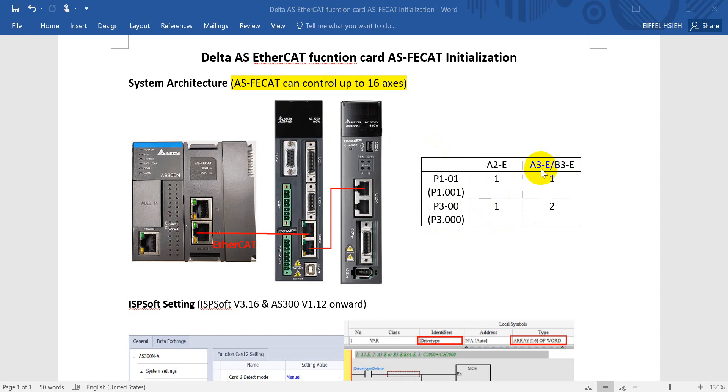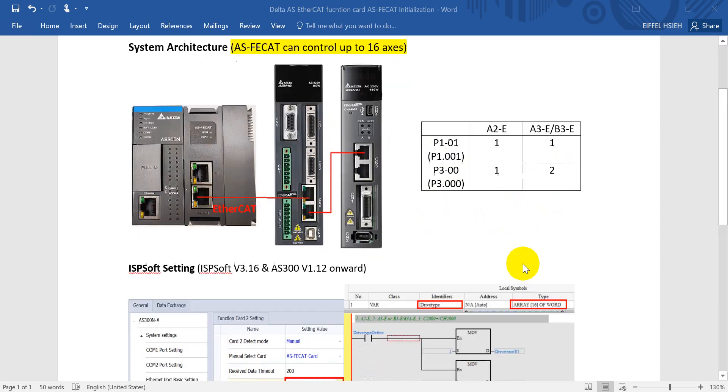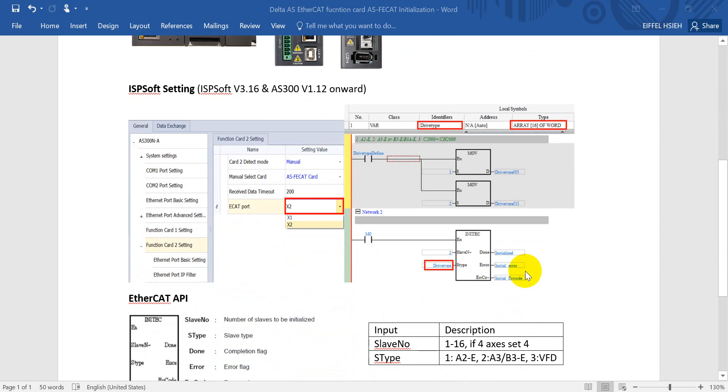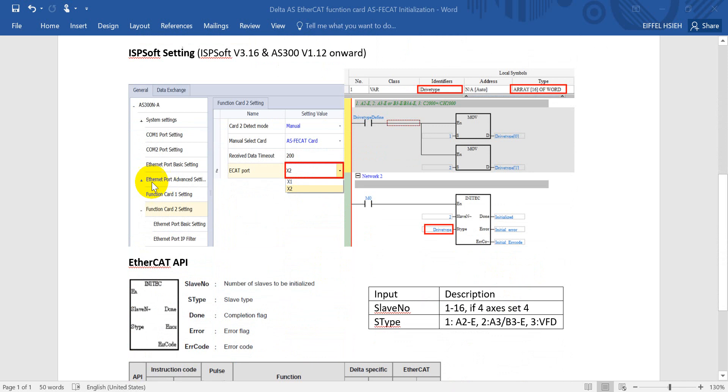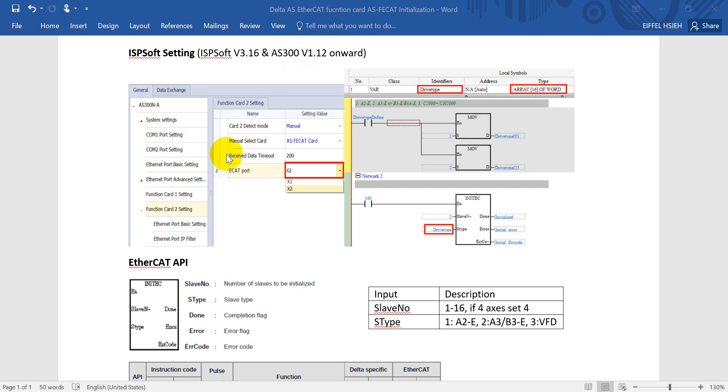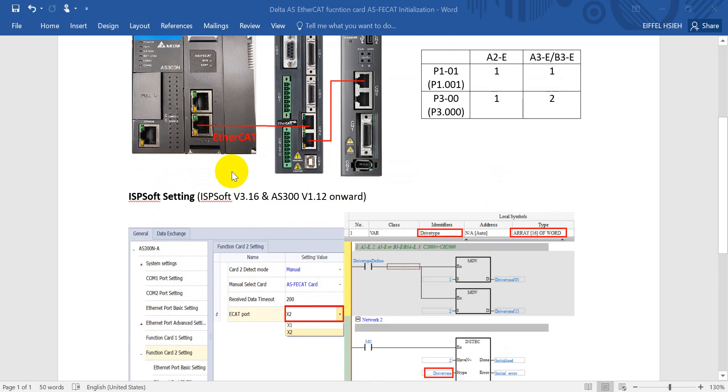Next we move to the ISPSoft setting. The ISPSoft here you must use version 3.16, and for AS300 series firmware should be version 1.12 onwards. For the hardware configuration, basically here just want to remind you have to set up the EtherCAT port. Today's example we use the X2 port, so for the setting inside please modify to X2. If you want to use X1 then you just modify the setting over here.